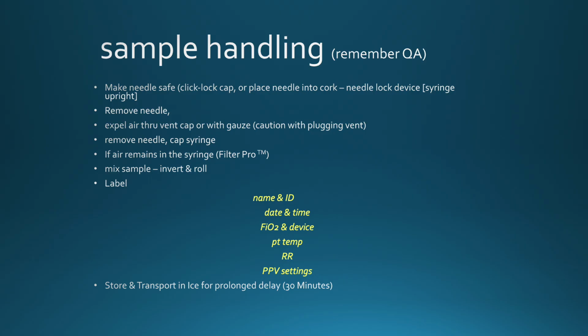Sample handling, we'll look at this more when we look at blood gas analysis errors. Remember, when you're acquiring your blood sample, you need to make your needle safe. Make sure that the needle cover is locked in place. The needle needs to be prevented from being exposed because of the risk of somebody getting a sharps injury. It has been in a patient, so blood-body fluid considerations and risks are associated with unsafely managed needles and other sharps. Needle lock devices are certainly the preferred method as a safety apparatus to be included with your equipment needs.